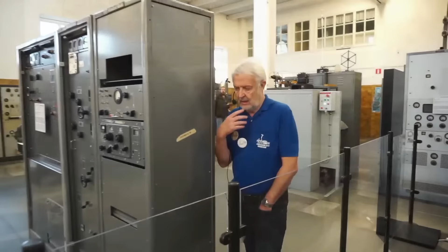We have done some preparations. We have controlled that all the machines are running well and that there is oil in all the bearings. Here there are no ball bearings in the machines, just plain bearings, so the lubrication is of great importance. We have also connected the station to a transformer outside in the transformer room.